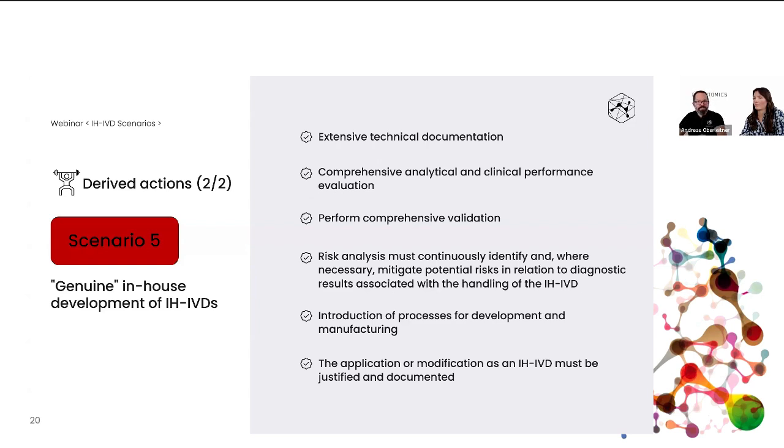From the performance evaluation, very similar to manufacturers. I mean, it's your device. You really developed and created it. So therefore, you need to perform all of the things which are needed in a pretty comprehensive way, I would say. The risk analysis from the beginning, maybe even including your manufacturing processes and maybe even your developing processes. You need to potentially introduce more SOPs, as already said, on this development process, on the manufacturing processes, etc., how to perform the quality checks and everything which is applicable.